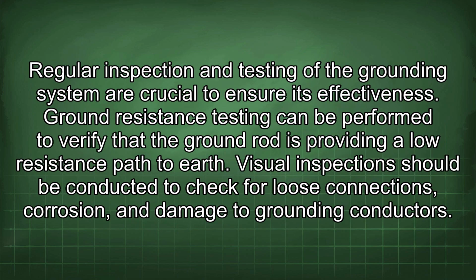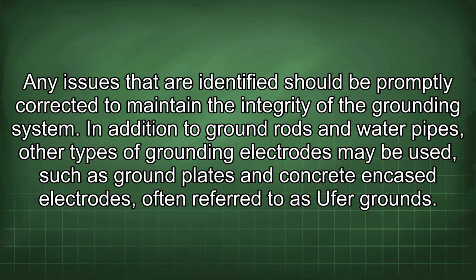Regular inspection and testing of the grounding system are crucial to ensure its effectiveness. Ground resistance testing can be performed to verify that the ground rod is providing a low resistance path to earth. Visual inspections should be conducted to check for loose connections, corrosion, and damage to grounding conductors. Any issues that are identified should be promptly corrected to maintain the integrity of the grounding system.